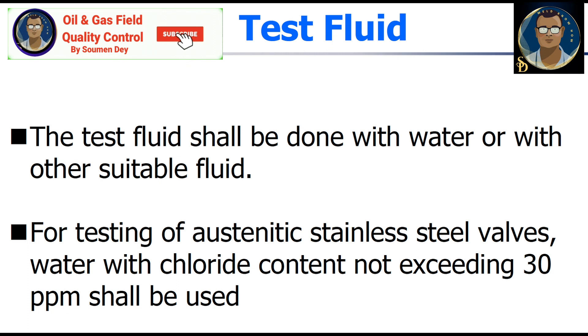What will be the test fluid for the valve hydro test? The test fluid shall be water or another suitable fluid. For testing of austenitic stainless steel valves, water with chloride content not exceeding 30 ppm — in some standards it is also 50 ppm — shall be used.